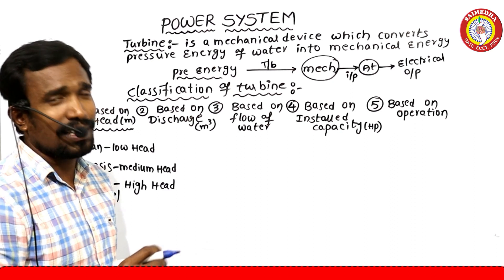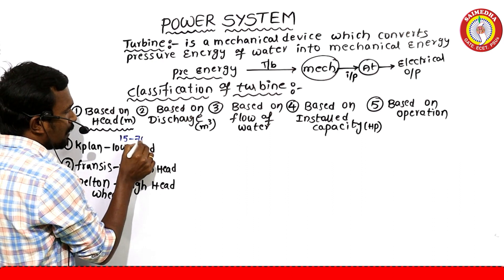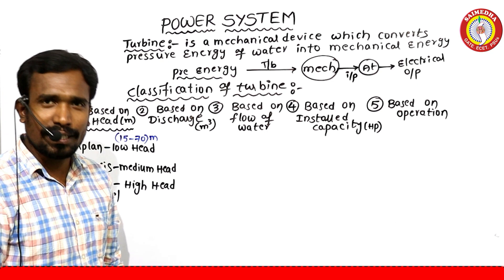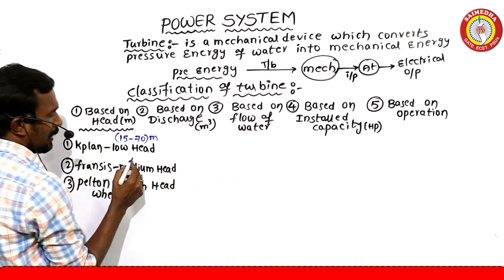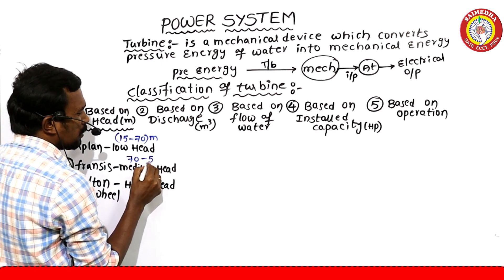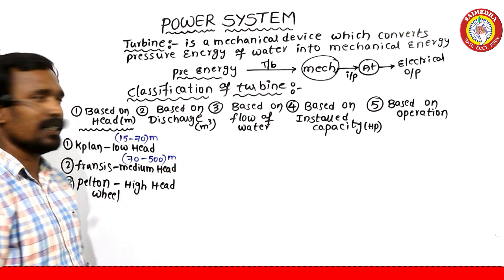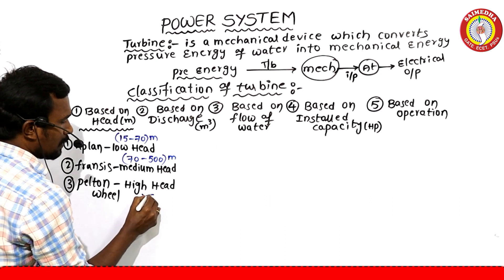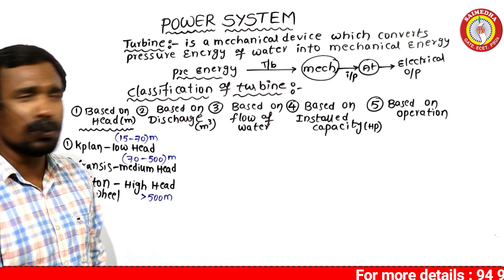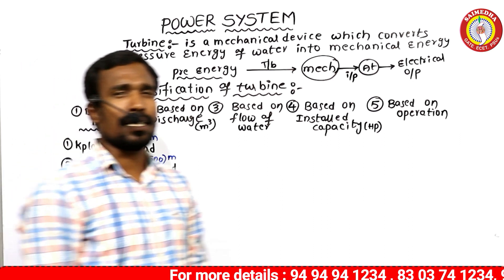What is the low head range? It is 15 to 70 meters of head. What is the medium head? It is 70 to almost 500 meters of head. Greater than 500 meters is the High Head Turbine range. So Kaplan, Francis, and Pelton Wheel are classified by these three head ranges.